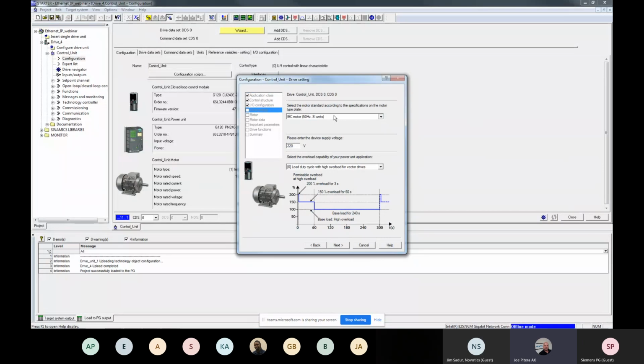We are going to select a NEMA 60 Hertz, SI units. We are going to use a 230 volt supply voltage here for our drive. And we have the overload capacity will be a low duty cycle with low overload for vector drives. You have your choice here with high overload. We have an S1 and an S6 duty cycle for internal uses. So in this case, we don't have a lot of overload on my demo unit.